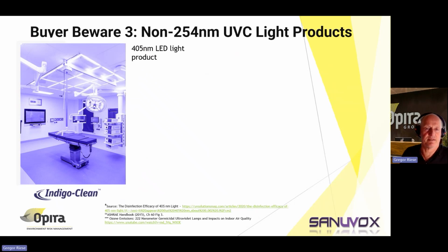There's also considerations regarding different products. This is my buyer beware part 3. At the recent IHEA conference in Adelaide, one of the suppliers was marketing a new product of 405 nanometer LED lights as part of a surgical installation with HEPA filters up here. And the 405 nanometer is supposed to disinfect the room, and it's much safer for any occupants in the room while the lights are on.